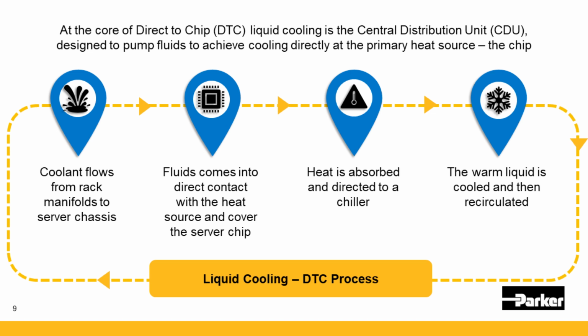The heart of this is the cooling distribution unit, a pumping unit that circulates fluid around to the chips and different areas where it's required. That coolant moves from the pumping unit or cooling distribution unit over to rack manifolds, and through those it goes to each piece of IT gear, where it directly interfaces with the chips through, usually, a cold plate, and then comes back through the manifolds to reject that heat to the environment somewhere.